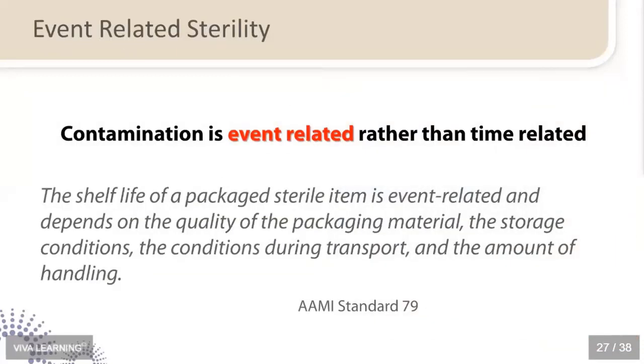So how long can we keep sterile packages stored? Years ago, it was a time-related event, and there are still some facilities that may have time-related rotation as their protocol. I'm giving you from the AAMI Standard that they're saying as long as a package has not been compromised during storage, the contents are remaining sterile. So event-related sterility: nothing happened to that pouch or pack. It wasn't dropped, it didn't get ripped, it didn't get some coffee splashed on it, it didn't get set in a puddle of water on the countertop. So contamination is event-related rather than time-related.